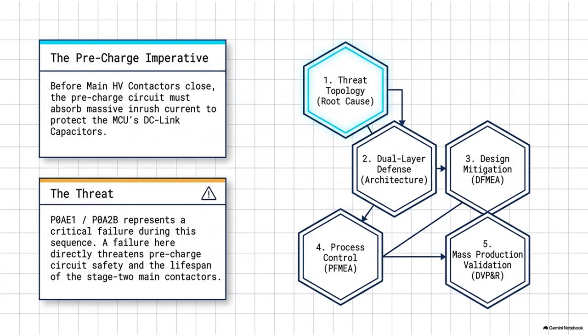So to prevent this, the engineers introduced the Precharge circuit. All right, the small bypass valve for our dam. Yes. Instead of slamming the main contactors closed, the BMS routes the initial current through a parallel bypass circuit. And this circuit contains a precharge resistor and a much smaller precharge relay. So by forcing the electricity through that resistor, we bottleneck that inrush current. We're artificially limiting the rate of change of the current, letting the capacitor fill up gently. Right. It allows the DC link capacitor to saturate gradually.